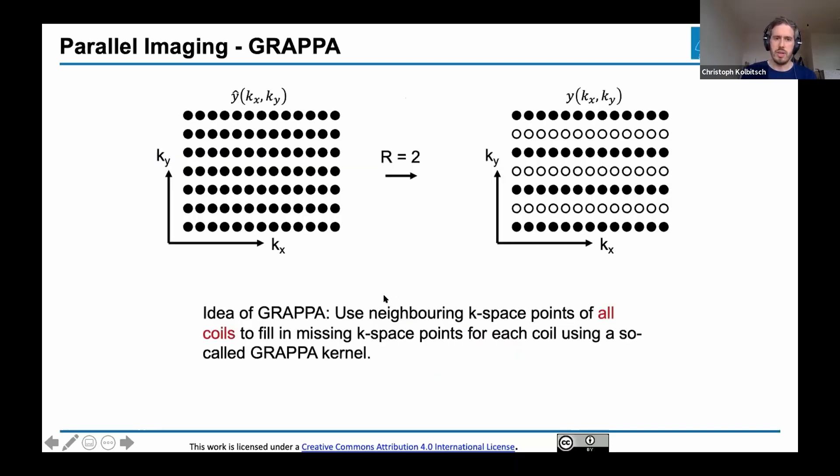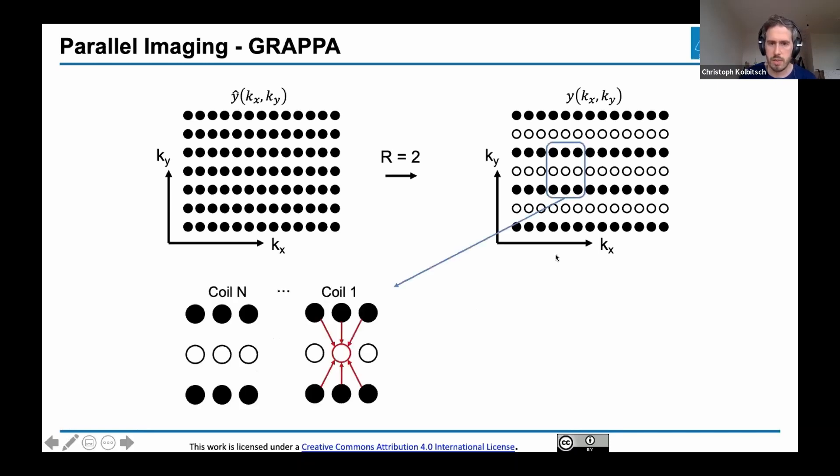This is the basic idea of GRAPPA. I don't have to acquire a full k-space. Here's an example of an undersampling factor of two, leaving out every second line. Then I use the points I've acquired to fill in the missing points. I can do this because I acquired it with multiple receiver coils, and I know the effect of these coils is that there's distribution of data from here onto neighboring k-space information.